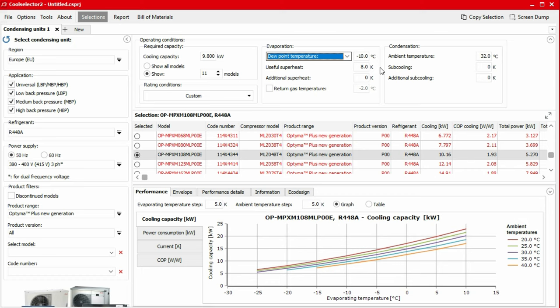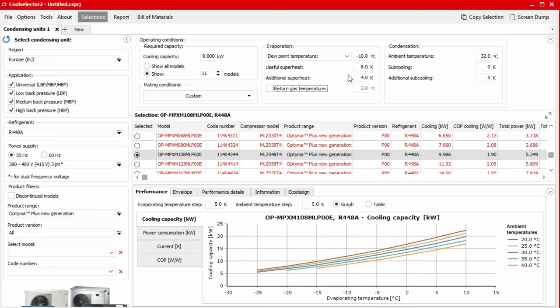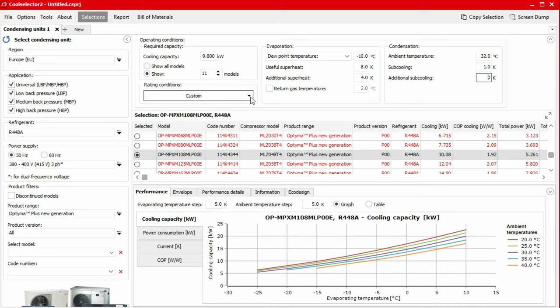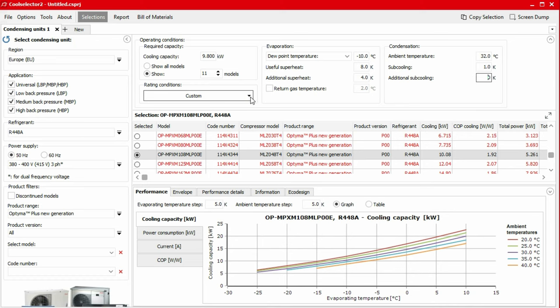We'll then input a useful superheat of eight kelvin and then an additional superheat of four kelvin. For the condensation, we'll specify an ambient temperature of 32 degrees Celsius and one kelvin for the subcooling. We also have the option to specify a rating condition with various options in the dropdown menu. For this example, we'll leave this as default.